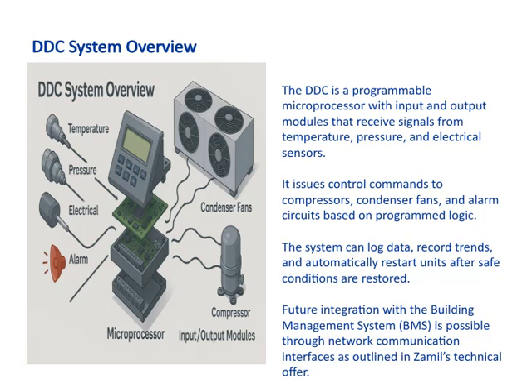Let's take a closer look at the DDC system overview. The DDC, or Direct Digital Control System, is essentially a programmable microprocessor that manages various building systems. It works with input and output modules that receive signals from different sensors, such as temperature, pressure, and electrical sensors. These signals are critical because they provide real-time data about the environment and equipment status. Based on this data, the DDC issues control commands to equipment like compressors, condenser fans, and alarm circuits.